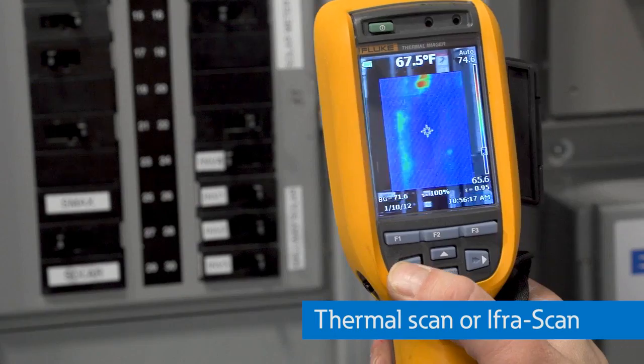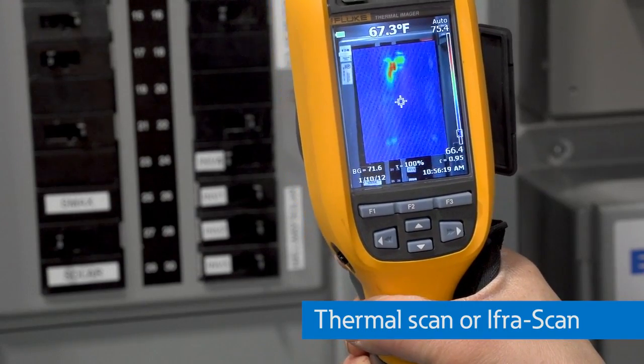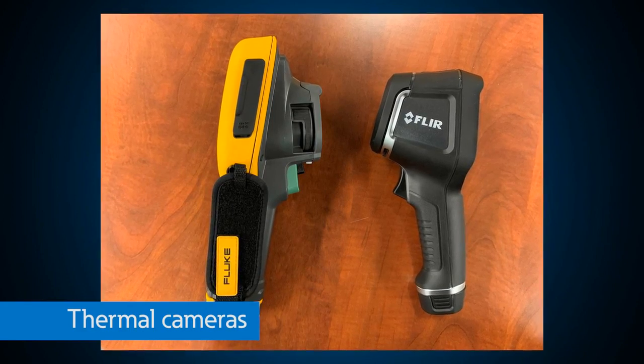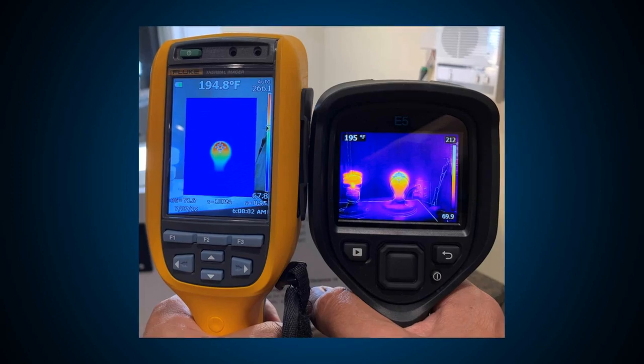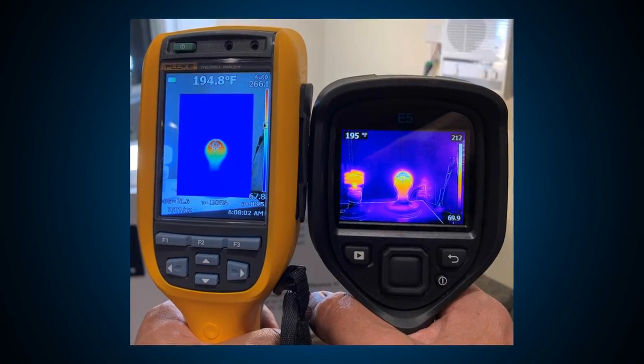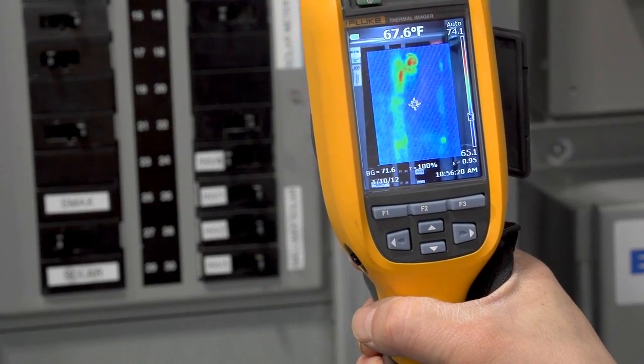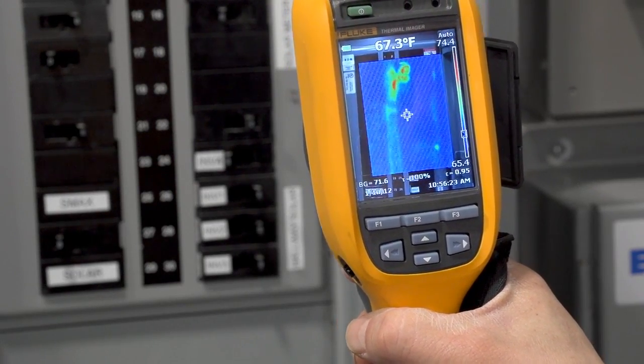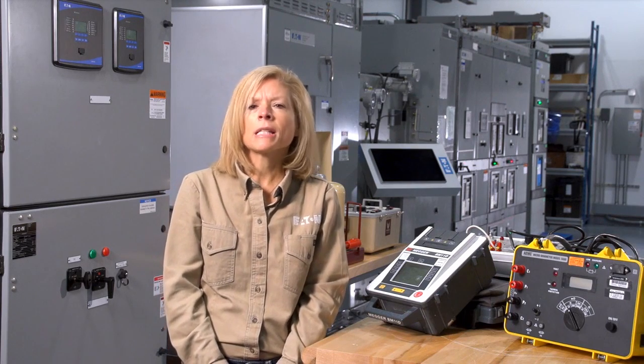Overheating of electrical equipment can be found by thermal scanning, often called infrascan testing, to look for loose connections or other problems. This is done by using a thermographic infrared camera to detect infrared energy or heat and converting it into an electronic signal. This signal is then made into a thermal image that can be displayed on a video monitor showing the temperatures of components in the picture. When one part of the equipment exhibits a hot spot, it often indicates a localized problem, like a loose connection or overload. Periodic scans help maintenance personnel evaluate and trend problem areas before they result in a failure or arc flash issue.